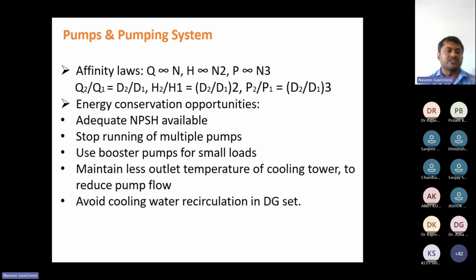So stop running multiple pumps. Sometimes while reducing the load, people are using both pumps, so it should be rectified. Use booster pumps. Maintain a lower outlet temperature of the cooling tower for getting the coolness of the pump. What is our supply arrangement for giving the coolness?